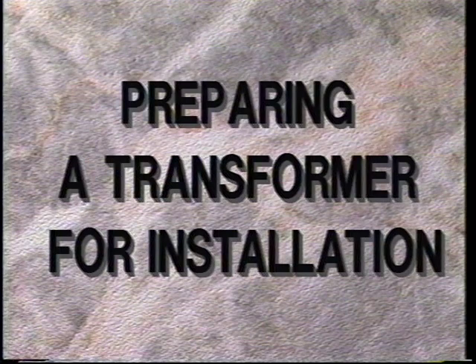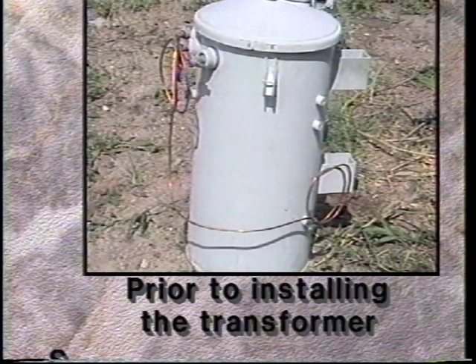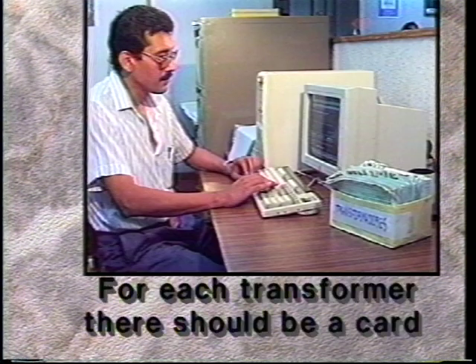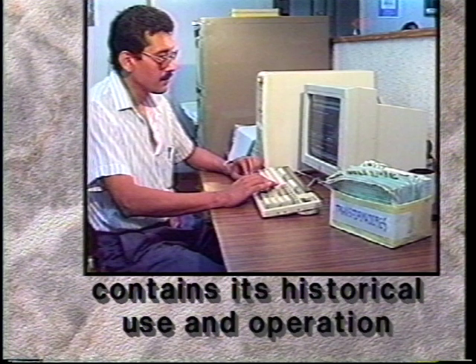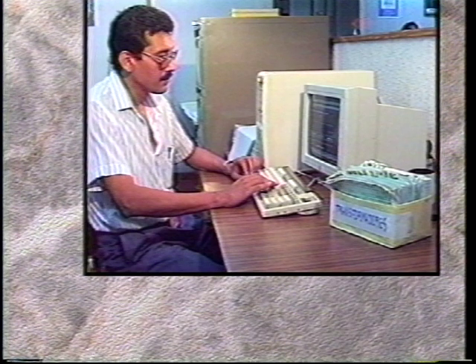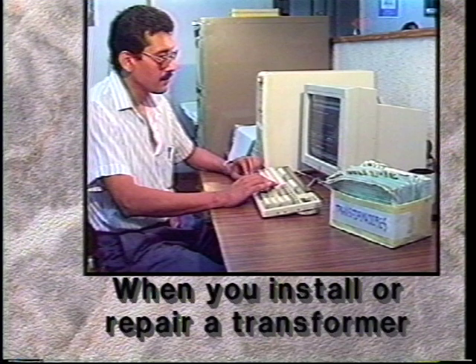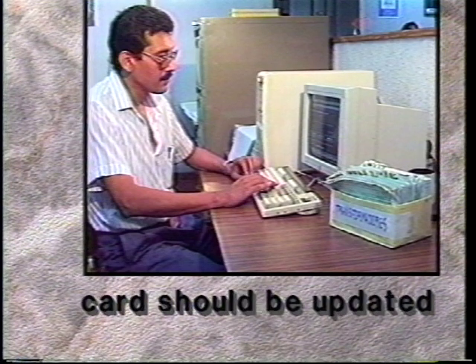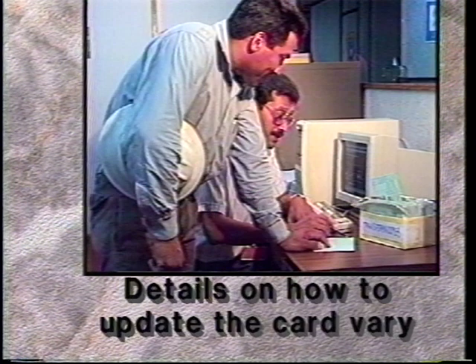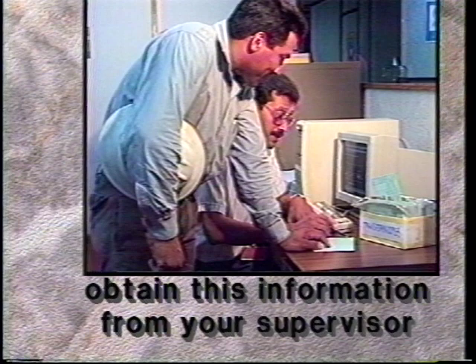Preparing a transformer for installation. Certain steps must be taken prior to installing the transformer. For each transformer, there should be a card that contains its historical use and operation. When you install or repair a transformer, the card should be updated. Details on how to update the card vary from company to company. Obtain this information from your supervisor.